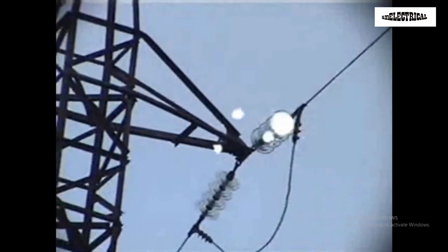If the conductor is very new, that means polished and smooth, then the glow will be uniform throughout the conductor. But in case of old rough conductors, at the very rough points on the conductor, the violet glow will appear brighter. In case of DC supply, as there are two different conductors, positive and negative, the positive conductor will glow uniformly and the negative one has a spotty glow. These are the results of corona which we see.